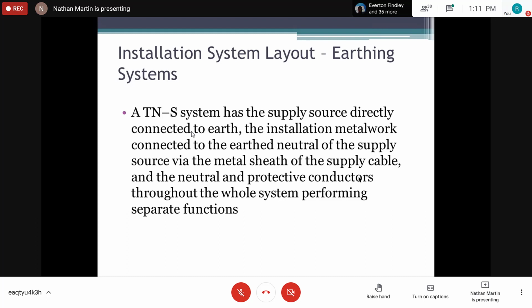So we're going to look at them in diagram now. We're just telling you what the wording means, right? Via the metal sheath of the supply cable. So for this type of installation, the supply cable might be an SWA cable, and we are saying that the source and the neutral are connected via that metal sheath, right? And the neutral and protective conductors throughout the whole system perform separate functions, right? So they are not tied in at any point.